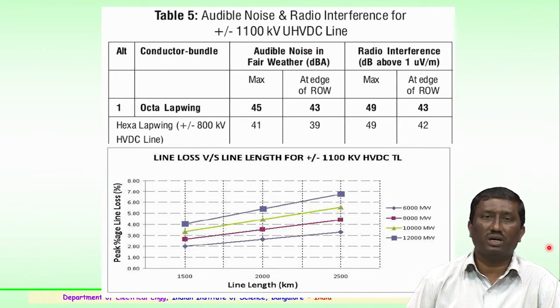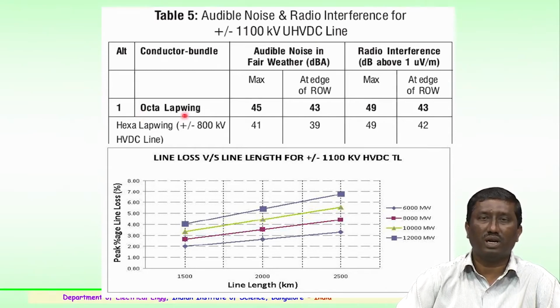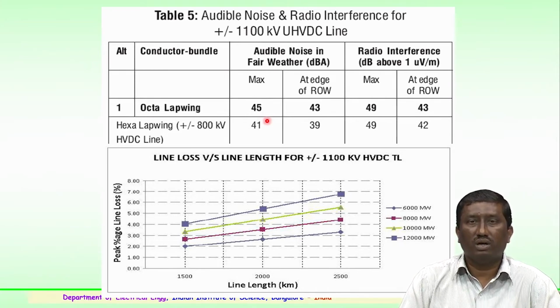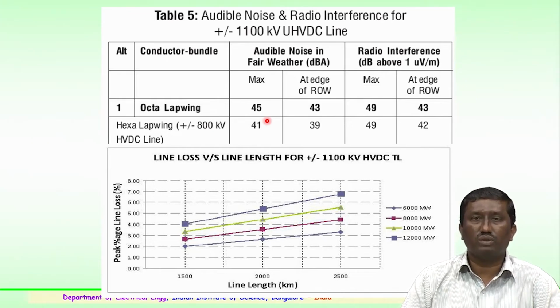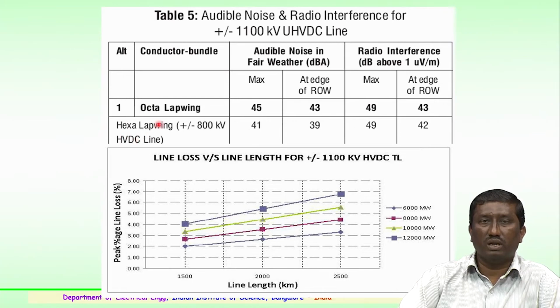Here you are again comparing with the 8 conductor lapwing type of conductor arrangement, which is 38.05 dimension. You see that the maximum estimated audible noise should not exceed 45 decibels, and at the edge of the right of way it should not exceed 43, which is the estimated value. And going in for hexa, that is a 6 bundle lapwing presently being used for 800 kV, the values are 41 and 39. So, a marginal increase has been seen by using the 8 conductor lapwing conductor.